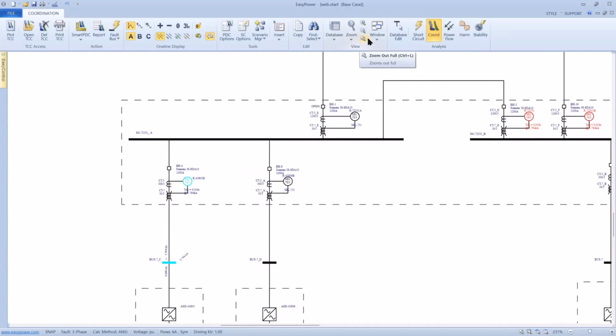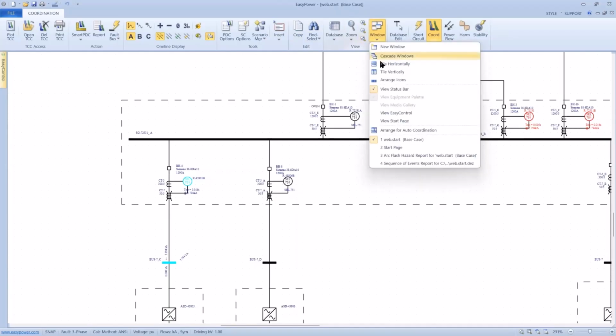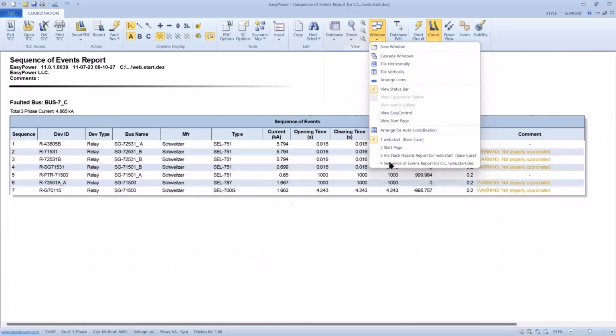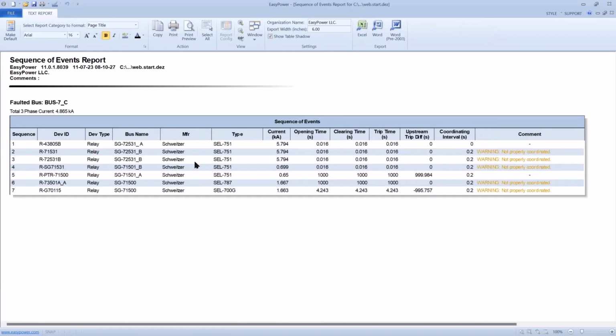Well, again, when I did that report, it shows up under my list of windows. If I bring it up, it shows me all the relays that are in series with this particular bus upstream, and none of them look like they're in good shape as far as coordination. So this is where I'm going to be focusing, at least for the short term, to see if I can get some first pass parameters.